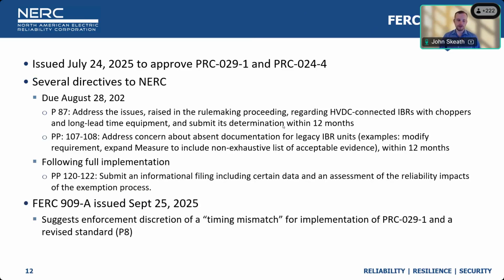After the development of PRC-29, we were issued FERC Order 909, which approved PRC-29-1 and PRC-24-4, the counterpart for the synchronous facilities that was also filed at the same time, but it also included several directives to NERC. And so on August 28th, and that's 2026, sorry, no, that's a typo there. There are a few requirements. Paragraph 87 says that we need to address the issues raised in the rulemaking proceeding for FERC Order 909 regarding HVDC-connected IBRs with choppers and long lead time equipment, and to submit NERC's determination within 12 months.